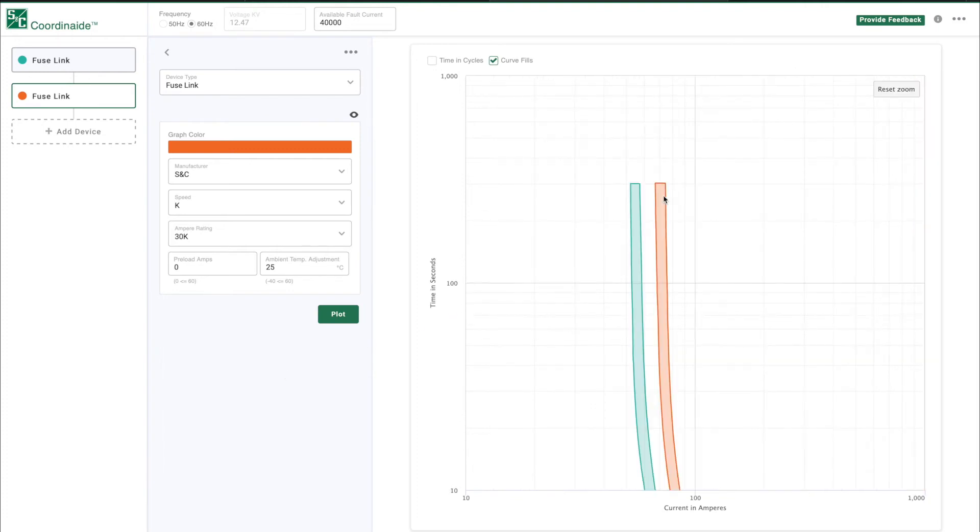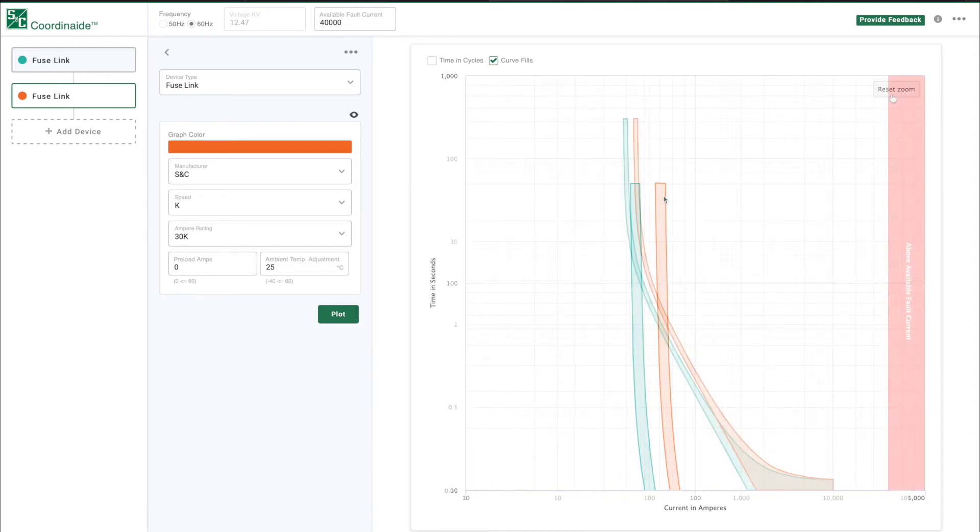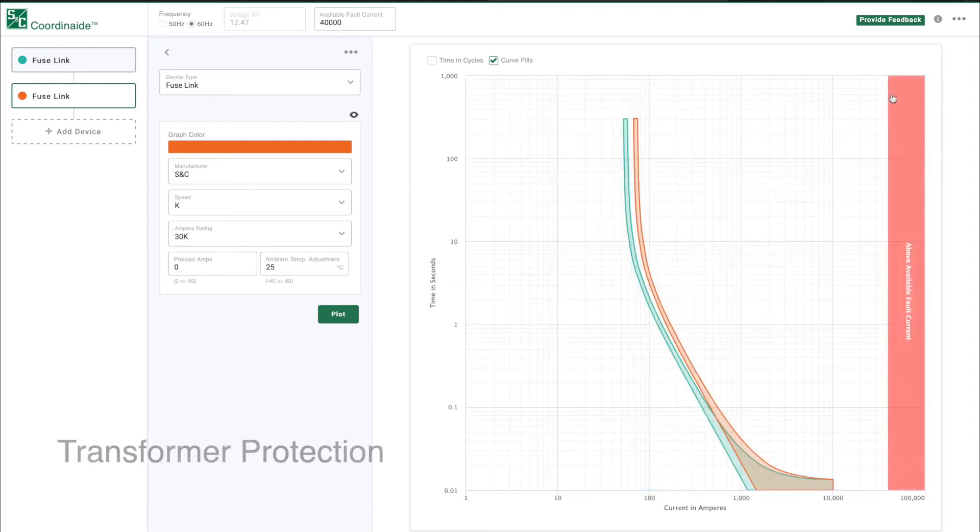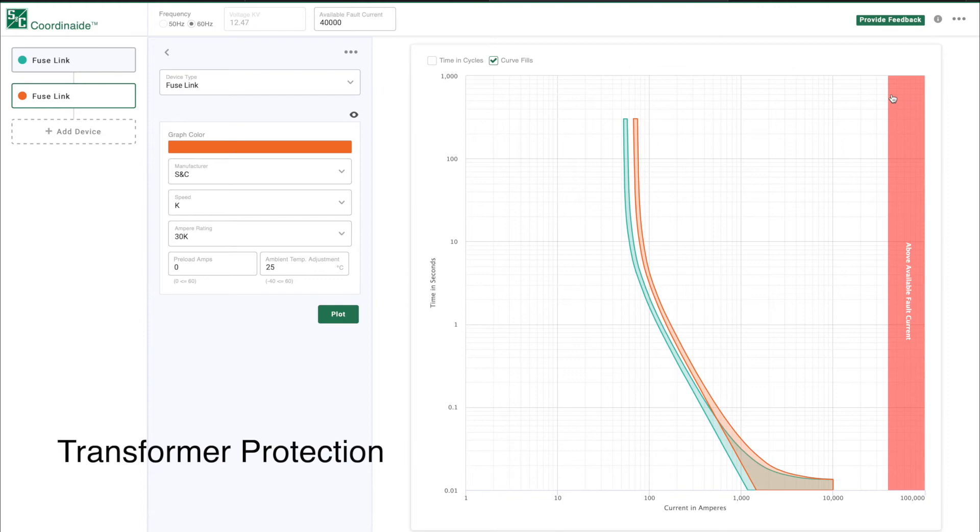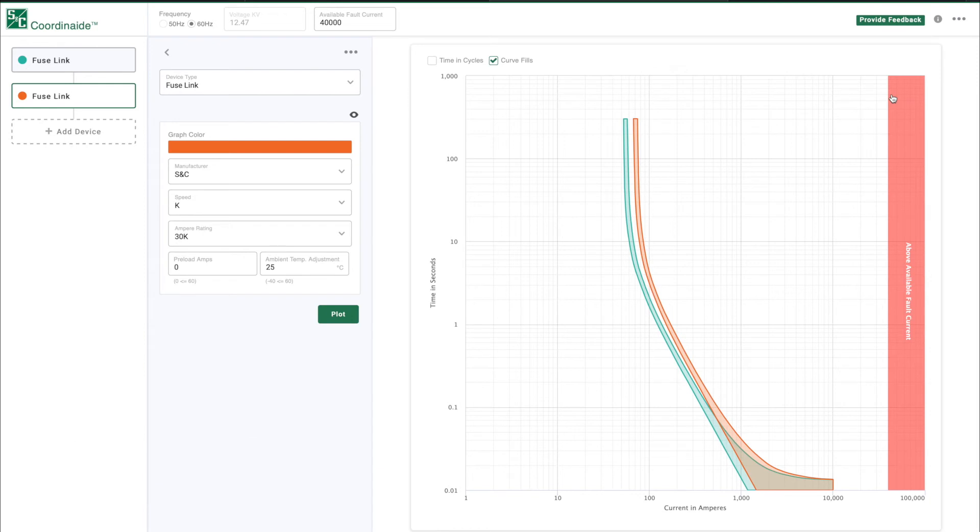That's a basic walkthrough of the software's functionality. Coordinaide software can also help solve more complex problems such as choosing a protection device for a transformer. Let's add a transformer damage curve to evaluate how well this fuse link will protect the transformer.